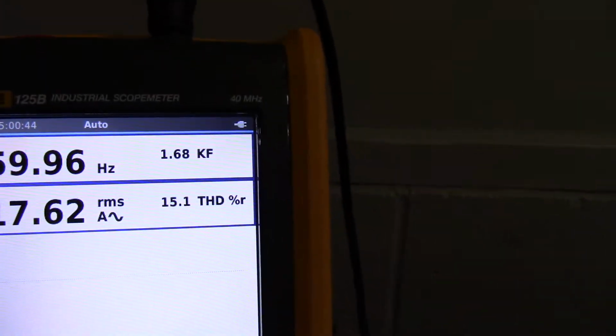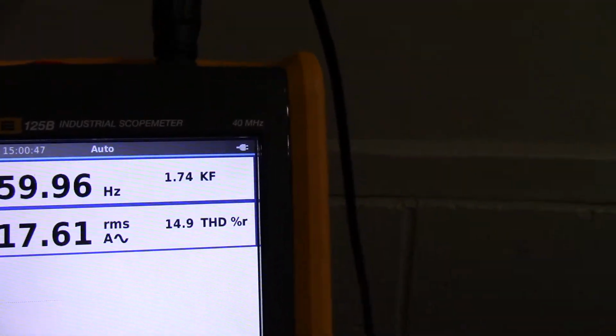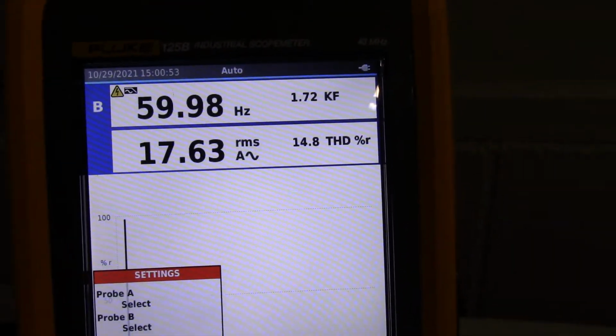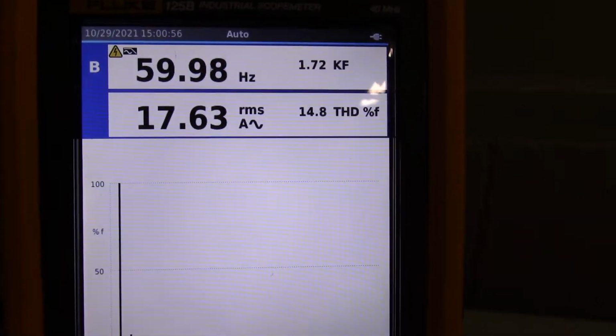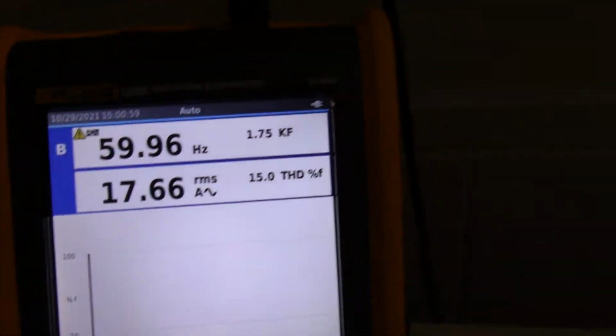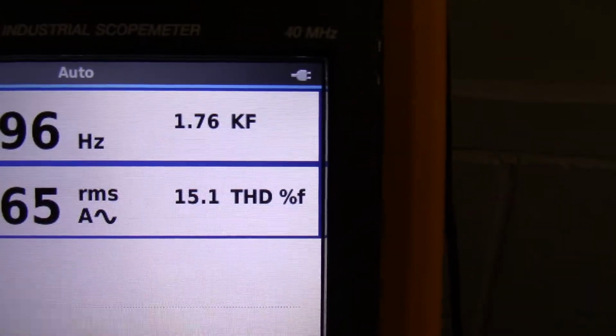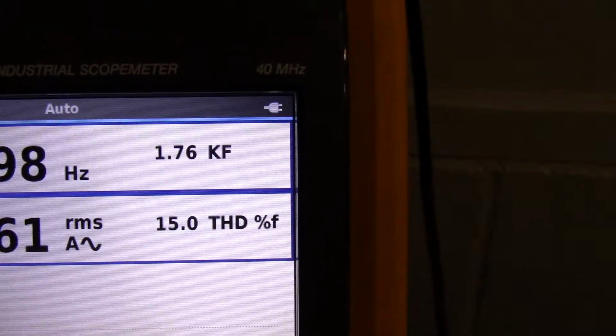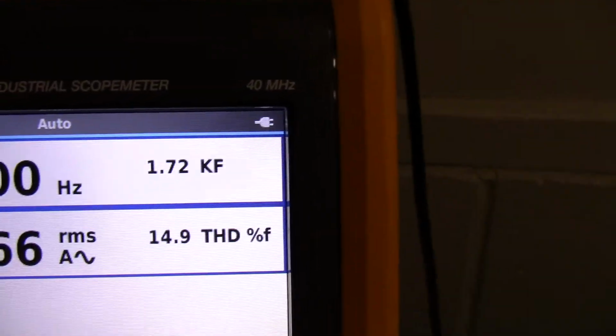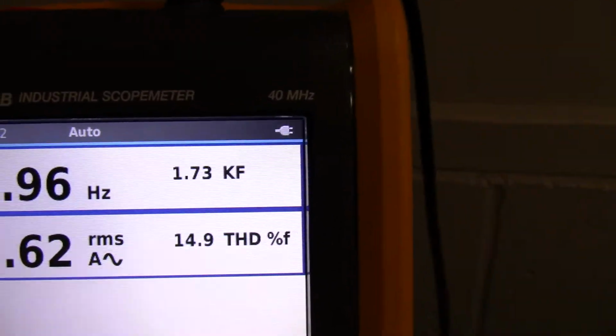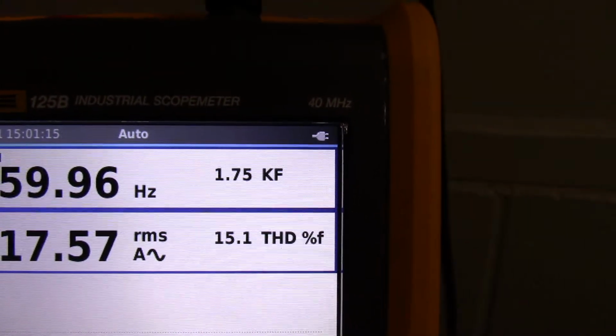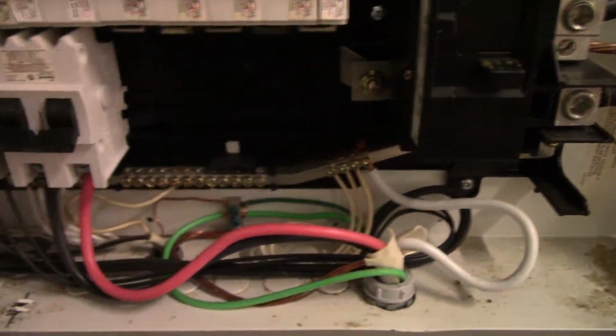Okay, now I'm going to change something here. What I just did is I changed the reading to read %F or % fundamental harmonics, so I can do a direct comparison to the Amprobe meter. So what we'll do now is we're going to try to find the load that's causing some of the harmonics, and I think I know which one it is. I think it's the VFD that's running in the background.